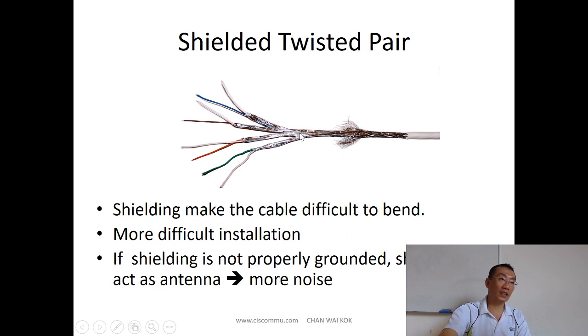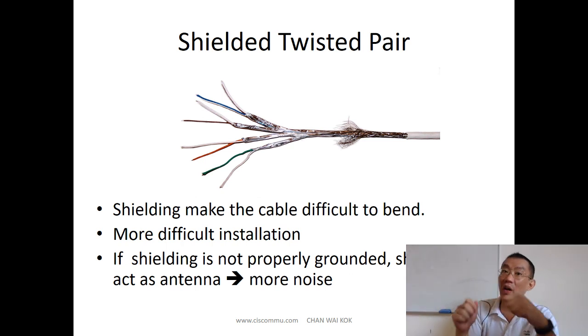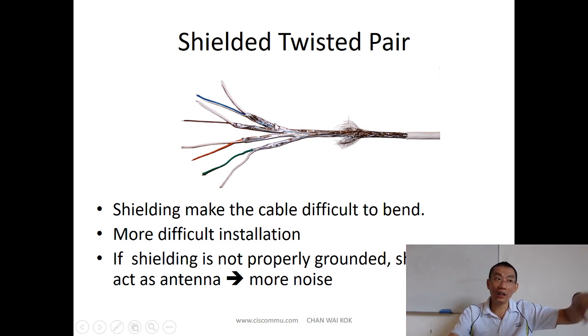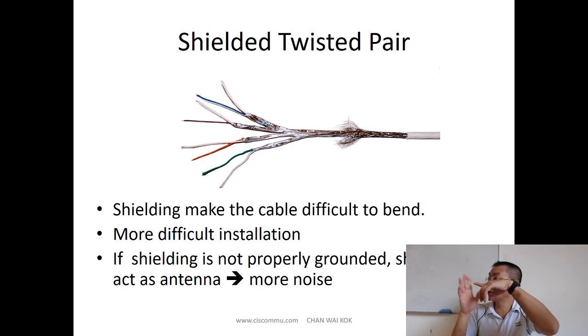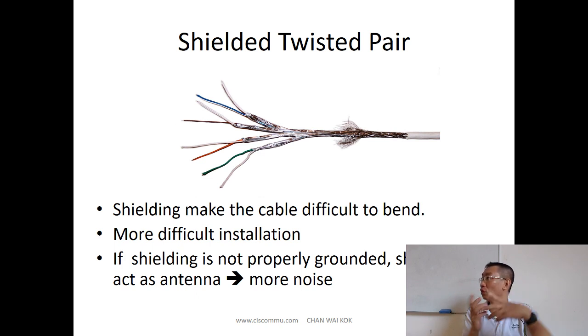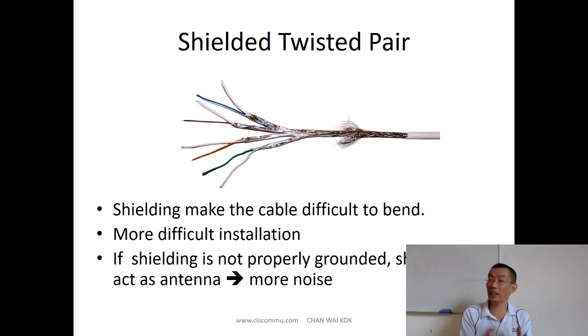Once you have shielding, the cable becomes more difficult to bend, so installation is slightly harder. Also, the shielding must be properly grounded — it must touch a metal plate on your patch panel so it's grounded to earth. If it's left open, it will act like an antenna and you'll get even more noise. That's the difference between shielded and unshielded.